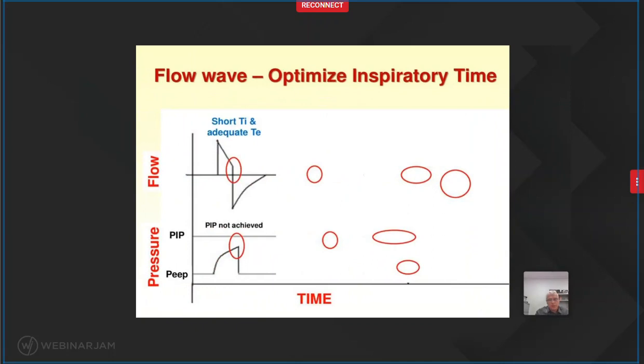Okay, so unfortunately the animation is not working here. I'm going to try to explain. So when the inspiratory time is adequate, your inspiratory flow should reach baseline and it should have a very, very tiny pause before the expiratory time begins. Okay, and if that's correct, then you should be able to achieve your PIP.